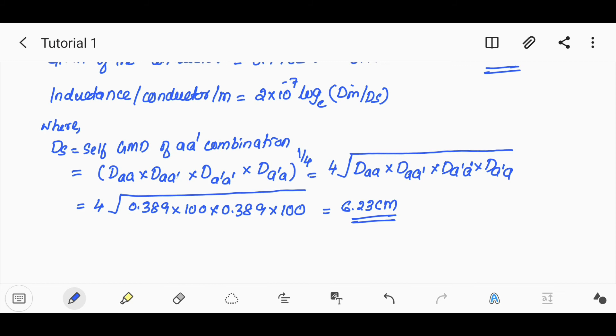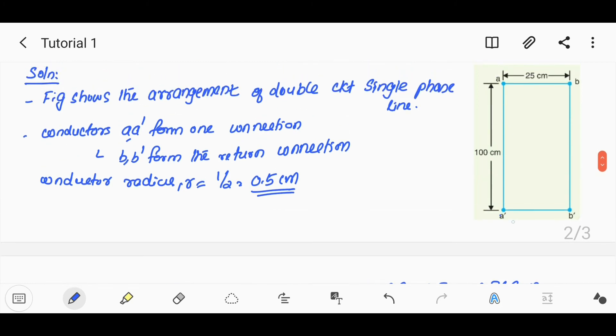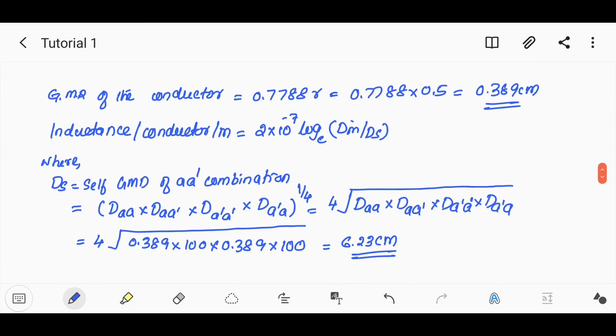The distance between A and A' is 100 cm, and the GMR D_AA is 0.389 cm. So Ds = fourth root of (D_AA × D_AA' × D_A'A × D_A'A'), giving 6.23 centimeters as the self-GMD of the A, A' combination.